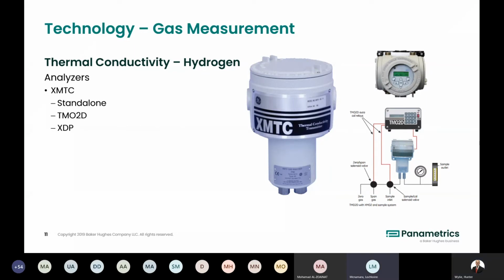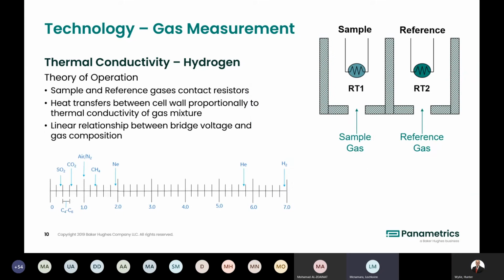Yeah, sure. For most of our applications, the two-port sealed reference is sufficient, but for certain applications where the purity of the gas to be measured is quite high, so in the 95 to 100 or the 98 to 100% range, it's preferable to use a flowing reference. You get a better signal comparison between the sample and the reference. The downside of the flowing reference is that you need to be using gas while you're doing that. It's a very low amount of gas, but you still need to consider it. But for most of our applications, the two-port sealed reference is what we use.